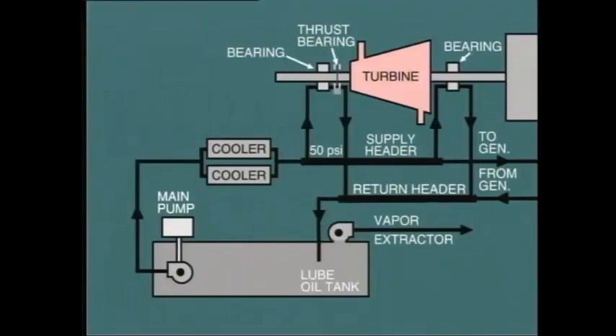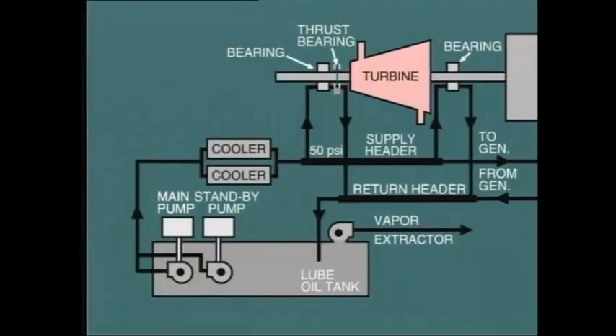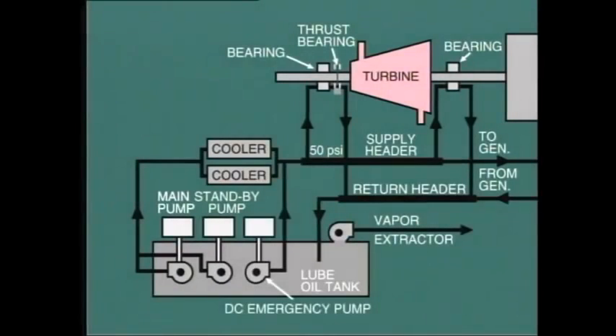The supply of lube oil is so vital to the operation of the turbine and generator that a standby pump must always be provided and maintained ready for startup on automatic control. But one question comes to mind. What would happen in the case that we lost all auxiliary AC power? This could happen, for example, in the case of a turbine generator trip in a facility with no station service backup. We'd then be faced with the prospect of the turbine generator running down without the circulation of lube oil, a condition that could conceivably damage all of the bearings. In order to prevent this potential disaster, many machines are equipped with a DC oil pump, which would be fed from the station battery in such an emergency.